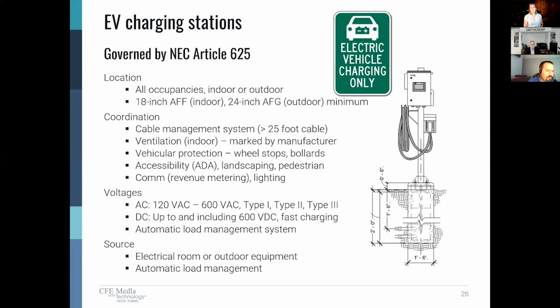And as we get into the voltages, there are AC, there are DC chargers. The AC fall into three different categories, but the voltage range is 120 to 600 volts AC. Type 1 is your typical in-the-garage residential, plug into a 20 amp outlet, and the charger is within that cable length between the plug and the vehicle. Type 2 is your more commercial installation, say at an employer parking lot, where you've got some Chevy Volts plugged in outside in the parking area. Those are typically type 2 installations.